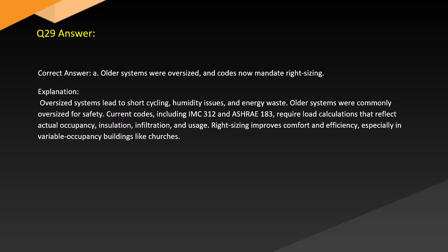Answer. Correct answer: A. Older systems were oversized and codes now mandate right-sizing. Explanation. Oversized systems lead to short cycling, humidity issues, and energy waste. Older systems were commonly oversized for safety. Current codes, including IMC 312 and ASHRAE 183, require load calculations that reflect actual occupancy, insulation, infiltration, and usage. Right-sizing improves comfort and efficiency, especially in variable-occupancy buildings like churches.